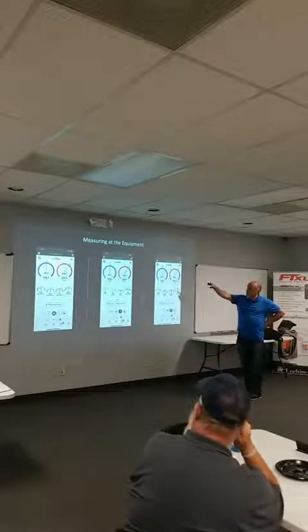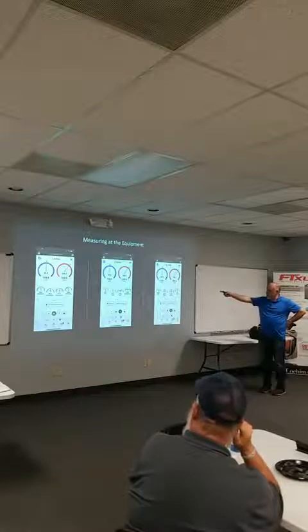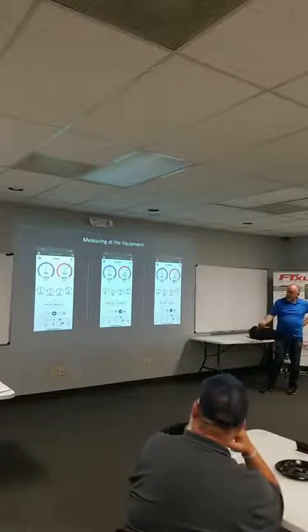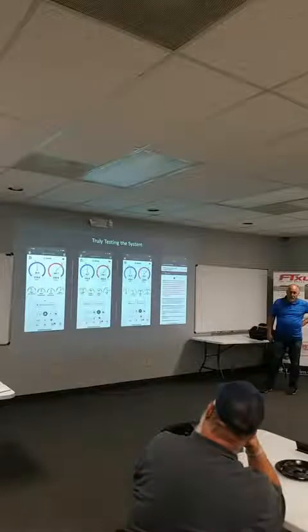75-degree air, 50% relative humidity. At the equipment, I'm running 13.5 SEER. Sucker's running great, running 33,000 BTUs of cooling, 23,000 sensible, 9,000 latent. That equipment's running great, right? Everything's running perfect. You just move that probe down into the house. It's now 70 degrees in the house. Humidity's the same. We're picking up sensible heat, right?